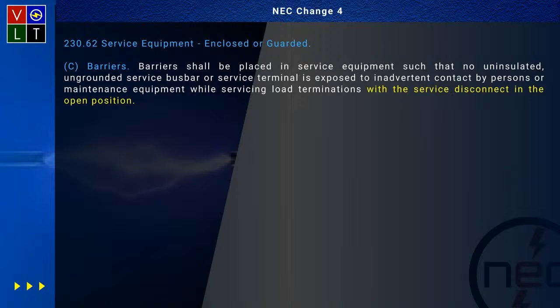No. And why is that important? One of the things, the barrier is there to protect you from what? Electrical shock. But if you got in there, something dropped or something, you think that little barrier is going to protect you from an arc blast? No, it's going to knock it right off there. And that's why they're telling you that the service equipment, when you're servicing those load terminations, it's in which position? The open position. That's why it's there.